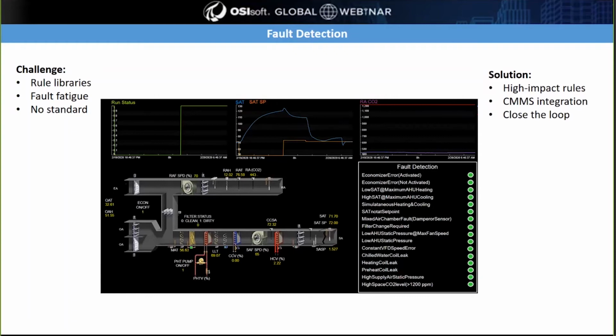The summary for fault detection is that there are too many rules out there, and applying too many results in a tremendous amount of faults that are hard to navigate, reducing the overall effectiveness of any fault detection system. The key is to select only high impact rules that eliminate noise and maximize the value of your fault detection deployment. Using the PI system to connect the outputs of a fault detection system to a maintenance management system allows high probability rules to automatically trigger ticket creation, and this is extremely powerful.